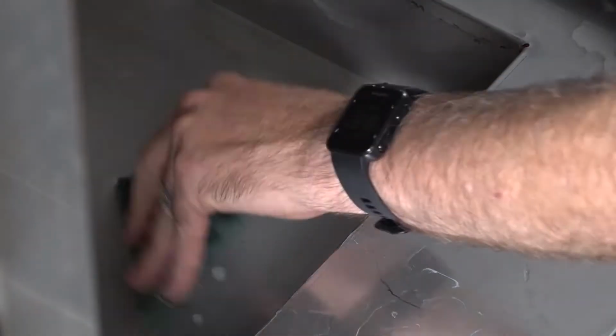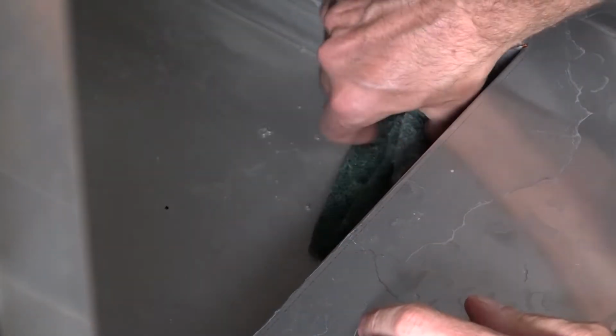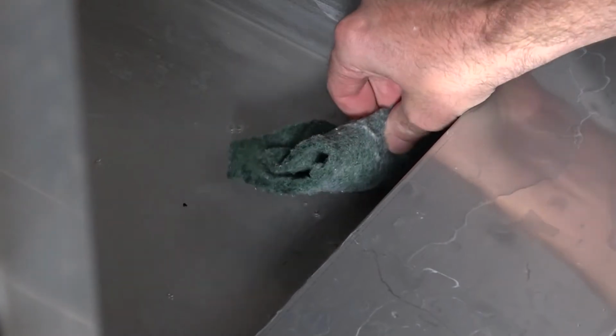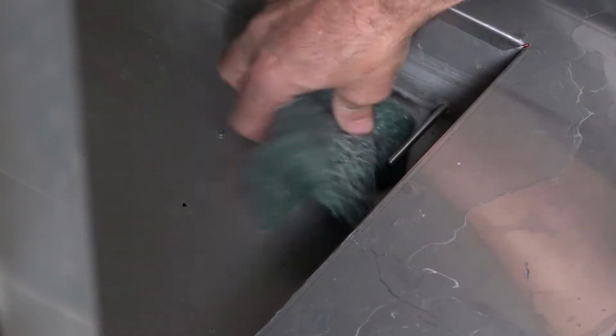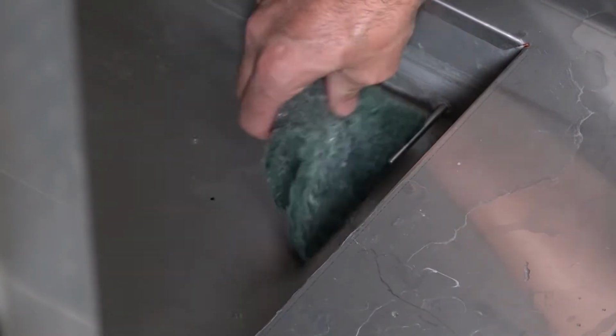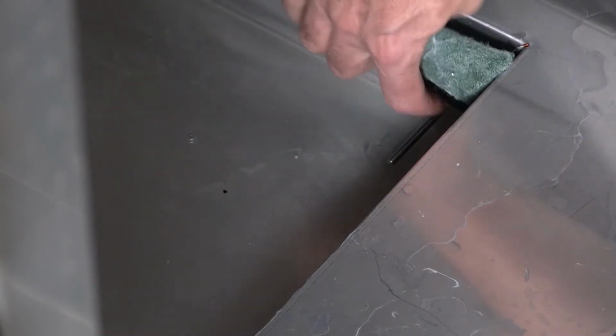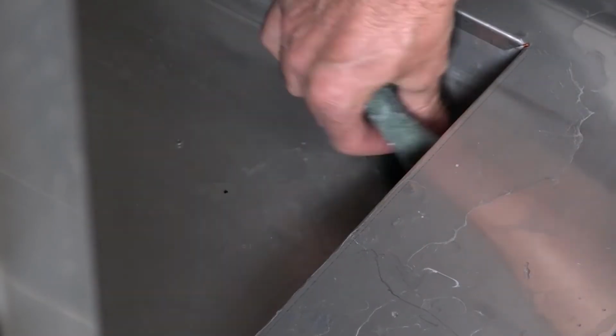Inspect for scale buildup in the evaporator pan, the water level sensor, and the water temperature probe. If scale is present, apply a descaling agent and remove any scale buildup. Ensure to read all warnings and follow the instructions listed on any descaling agent used.